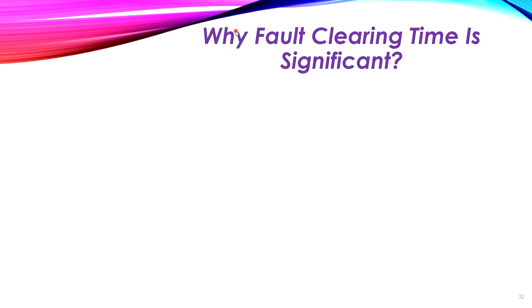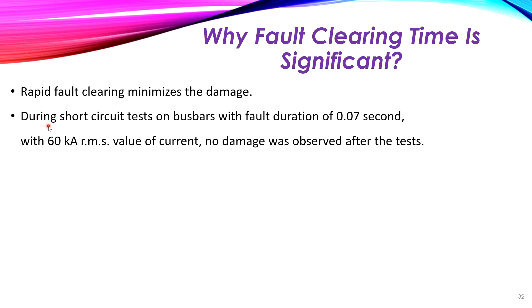Why is the fault clearing time significant? Number one: rapid fault clearing minimizes damage to equipment or the power system. As an example, during a short circuit test on bus bars with a fault duration of 0.07 seconds and a fault current of 60 kilo-amperes RMS, no damage was observed.